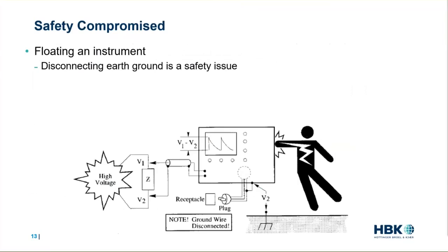Now, we've all probably floated an instrument. I know I did once in our lifetime, actually. Before floating an instrument many years ago while in college, I was designing an AC regulator circuit. And immediately after attempting to measure the AC output with a scope probe, I saw a spark trip the breaker because I shorted the AC output to ground. So then I decided to float the instrument, as they say, not realizing there were lethal voltages on the case of the instrument.